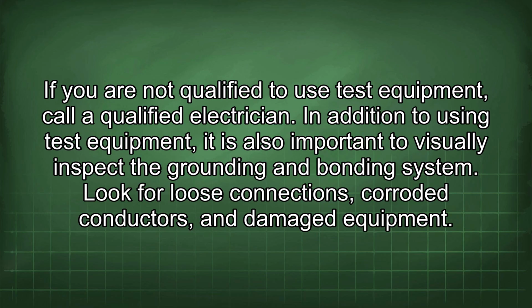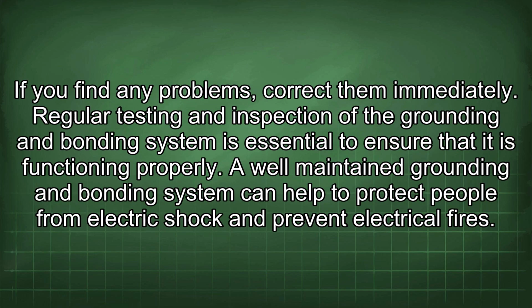In addition to using test equipment, it is also important to visually inspect the grounding and bonding system. Look for loose connections, corroded conductors, and damaged equipment. If you find any problems, correct them immediately. Regular testing and inspection of the grounding and bonding system is essential to ensure that it is functioning properly. A well-maintained grounding and bonding system can help to protect people from electric shock and prevent electrical fires.